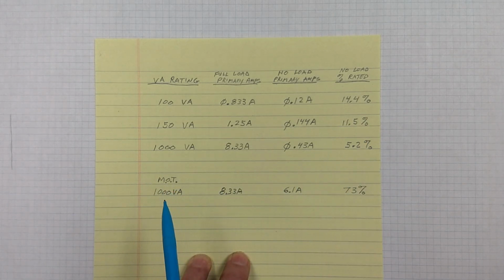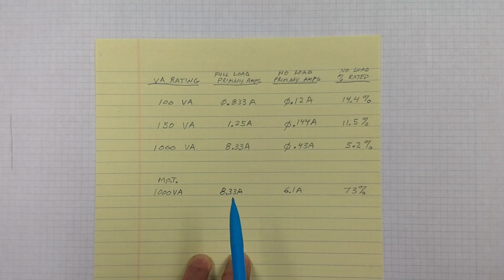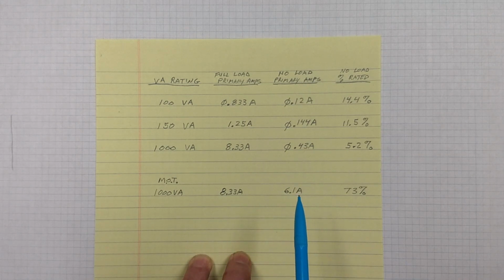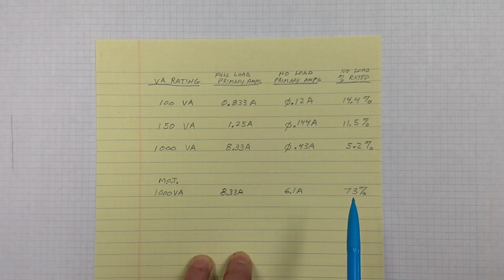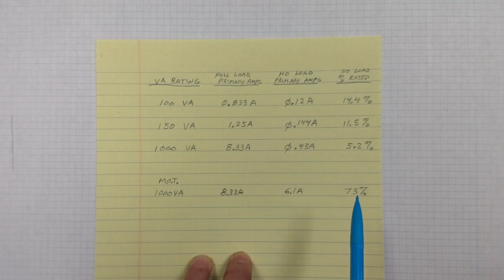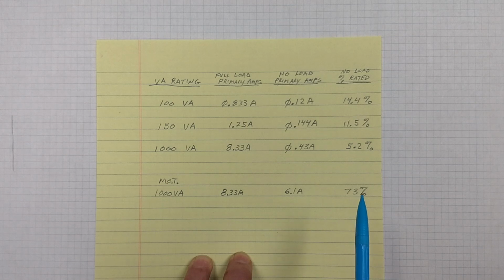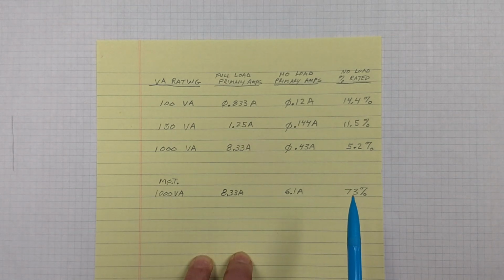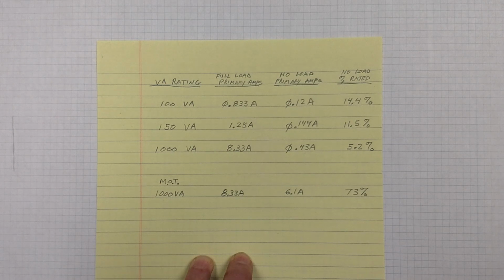Now, as I mentioned, the microwave oven transformers are really strange. We normally have a full load rating of 8.3 amps, and we measure 6.1 amps, and that's 73% of its full load rating when operating at no load. And let's take a look at why that is.